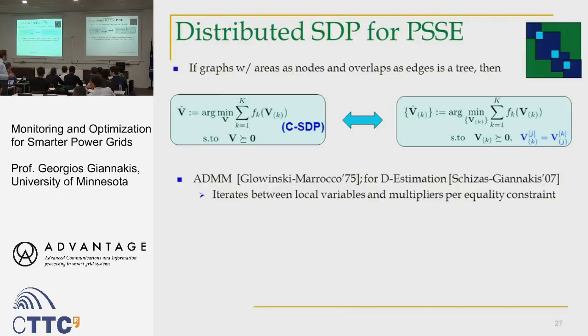What we have proved is that if your network is a tree, then there is no penalty in decentralizing it. So if you include the tie lines and you enforce positive definiteness in the extended voltage matrices, and you demand that the voltages shared, the bus is shared, have the same estimate, then solving the decentralized per-area state estimation is equivalent to solving the global state estimation.